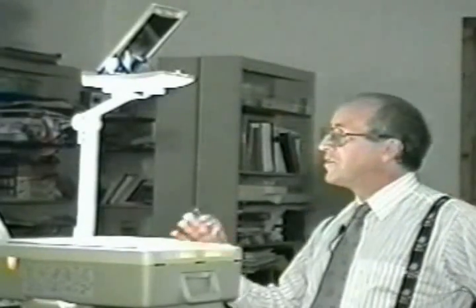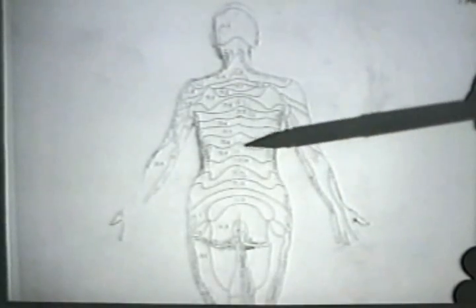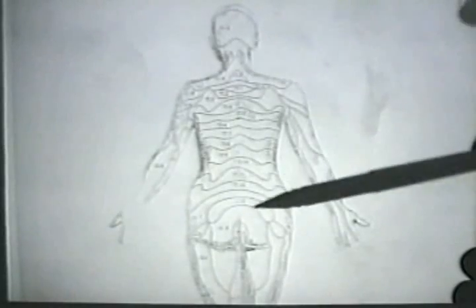Today's first video briefly covers the design and use of the C3000. The C3000 is a dual probe temperature scanning instrument with a unique ability to measure distance as you scan a person's back. Starting at the sacrum for a full spine scan, it measures position as you move up the spine. When the probes bump into the occipital shelf at the end of the paraspinal scan, that becomes the reference point for graphing to the computer.